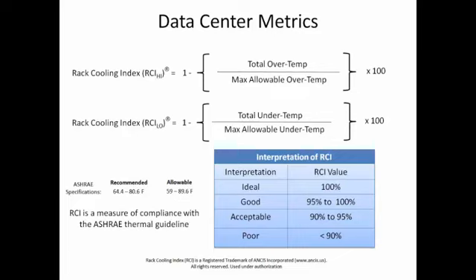And if you're below that, then your rack cooling index is going to be low, and that's a waste of energy. Same thing on rack cooling index on high. If you have any over temperature conditions, then this thing's going to be less than 100% as well, and that's not going to be good. So again, these are metrics we use to optimize the design in the data center. Magnus had quite a bit of work involved in these. You see his reference below. And I think these are very good.